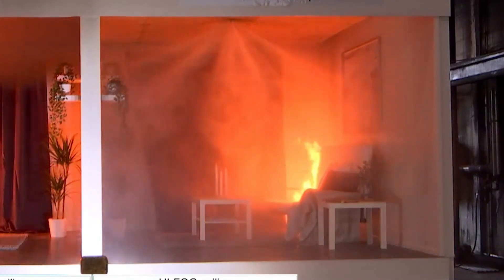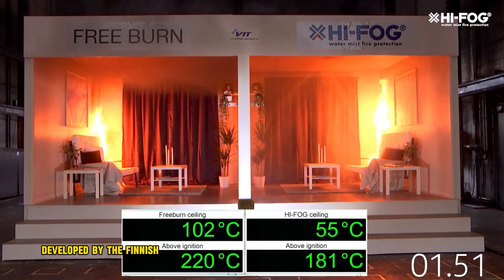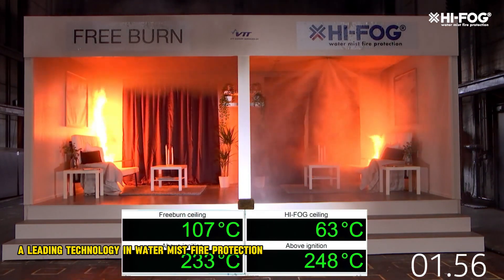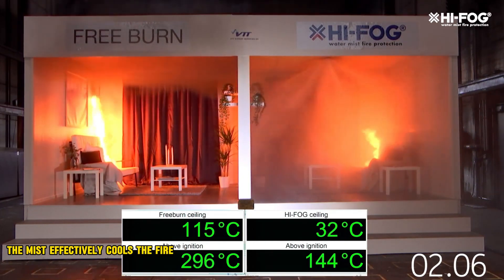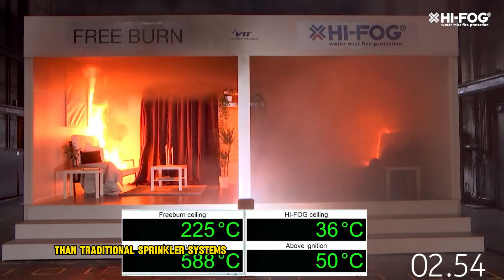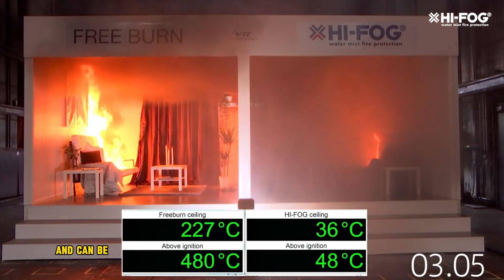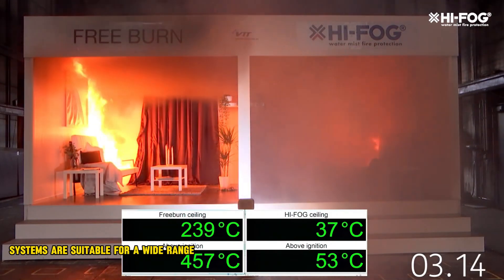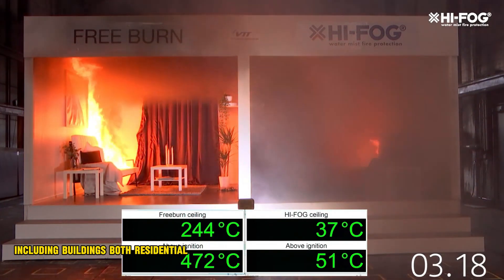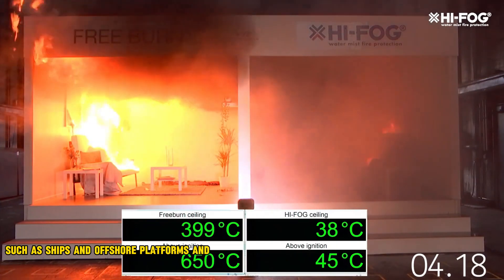HI-FOG refers to a specific type of high-pressure water mist fire suppression system developed by the Finnish company Marioff, a leading technology in water mist fire protection. HI-FOG systems use a fine water mist to extinguish fires, effectively cooling the fire and surrounding air to suppress the flames. They use significantly less water than traditional sprinkler systems — up to 90% less — and are safer for people as they don't displace oxygen or leave harmful residue. HI-FOG can be used for total flooding or targeted applications and is suitable for a wide range of environments, including residential and commercial buildings, industrial processes, marine environments such as ships and offshore platforms, and data centers.